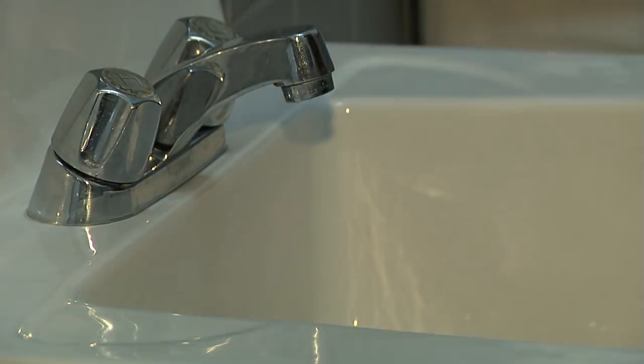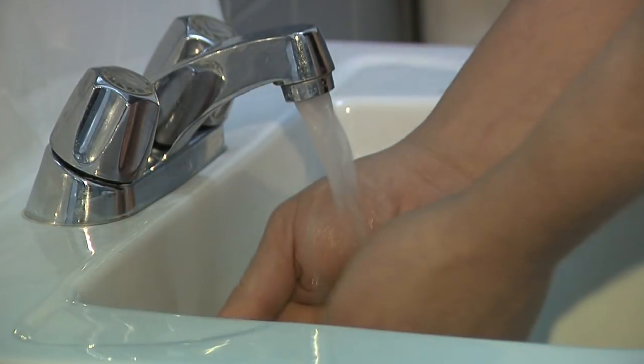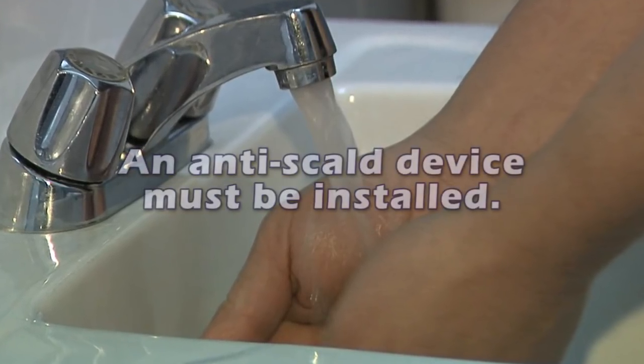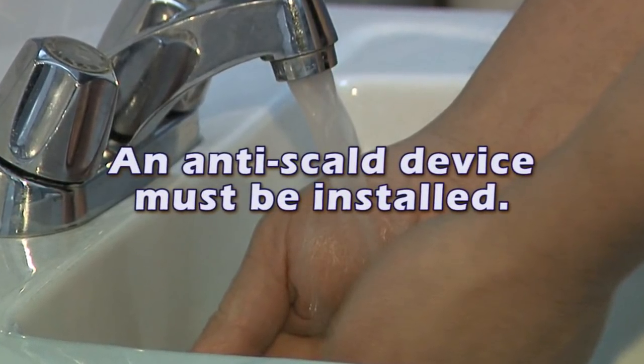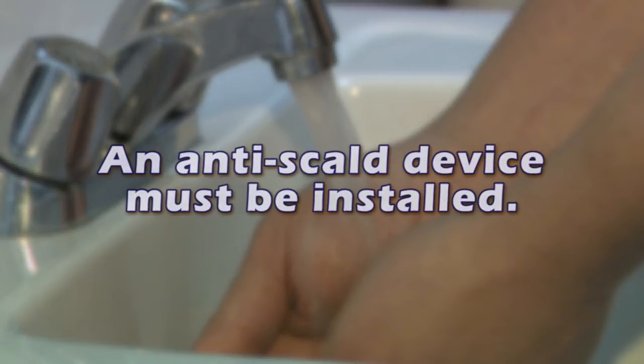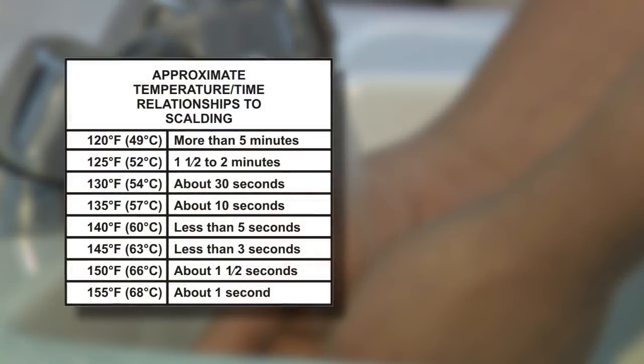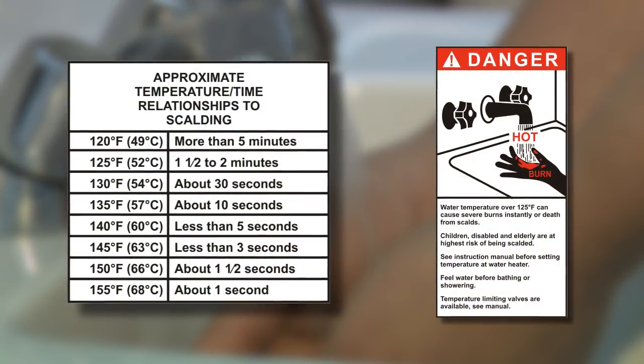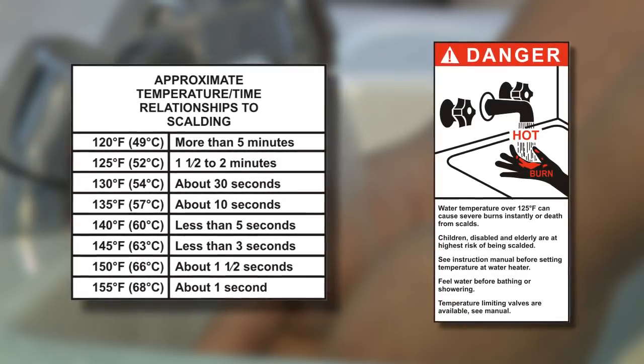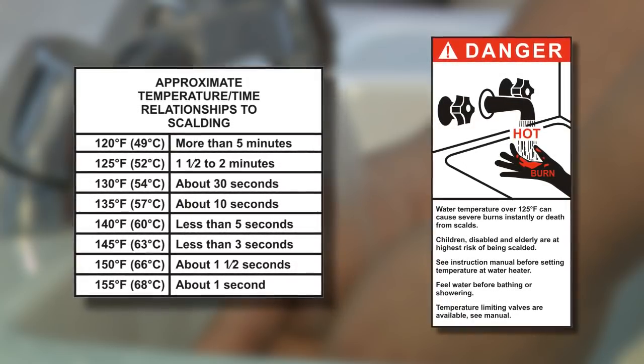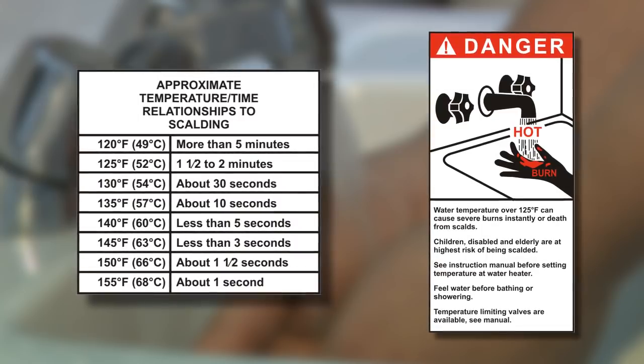If water temperatures higher than the default 120 degrees Fahrenheit are required, an anti-scald device must be installed for all domestic hot water outlets. Scalding can happen within seconds if proper precautions aren't maintained. Many state and local codes now require installation of these devices.